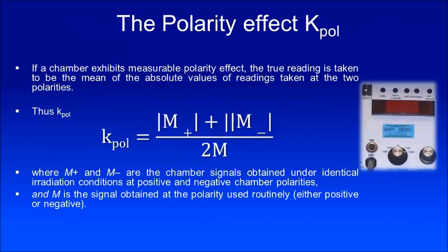The next one is the polarity effect correction factor. If a chamber exhibits a measurable polarity effect, the true reading is taken as the mean of the absolute values of readings taken at two polarities — positive and negative. You apply the normal polarity voltage, measure M+, then switch to negative polarity, measure M−, and take the mean to get K_pol. If the polarity effect for a particular chamber is larger than 3%, please don't use it — get it corrected. Polarity effect cannot be too high.